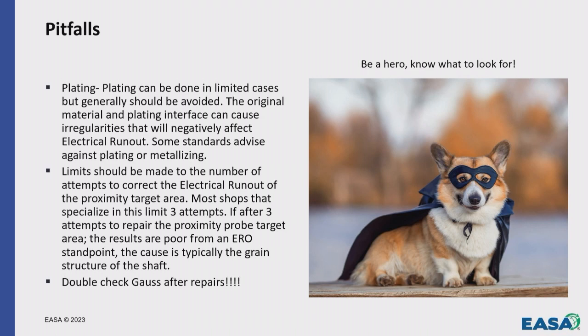I have heard of people that have made sleeves that were over an 1/8 inch thick and applied those, and that worked. But I don't have experience with it, and generally speaking, it's not recommended to plate, coat, or do anything on a prox probe target area. It will affect it. So if it's something you've got to do, that's just something you need to discuss with the customer first.